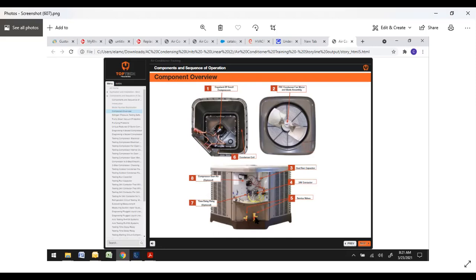Also, by your service valves here, you have a little half moon behind your service valves that gives you access into the compressor chamber there. Two screws right here. You can reach in there. You can check reversing valves on heat pumps. You can reach in there and check your compressor temperature. Any number of things you need to get inside for without having to take the top off.